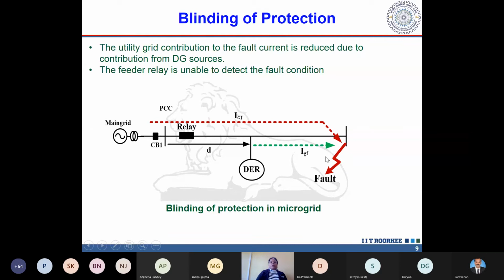Now, for the time being, just think that there is no presence of DER. That means the fault current, I fault, is equal to IGF, isn't it? The fault current contributed by the main grid. But now let us say the DER is present, so the fault current will remain constant, like let us say 10 ampere.